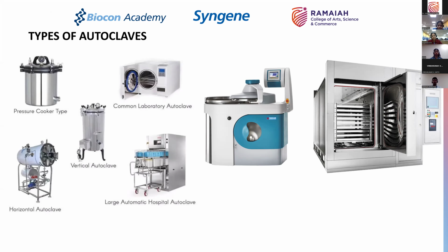These are very well, of course, systems which are used in the industry because you have steam generators, the boilers are there, and therefore it is easier for you to just send that steam across, not to worry about water and the level of the water.